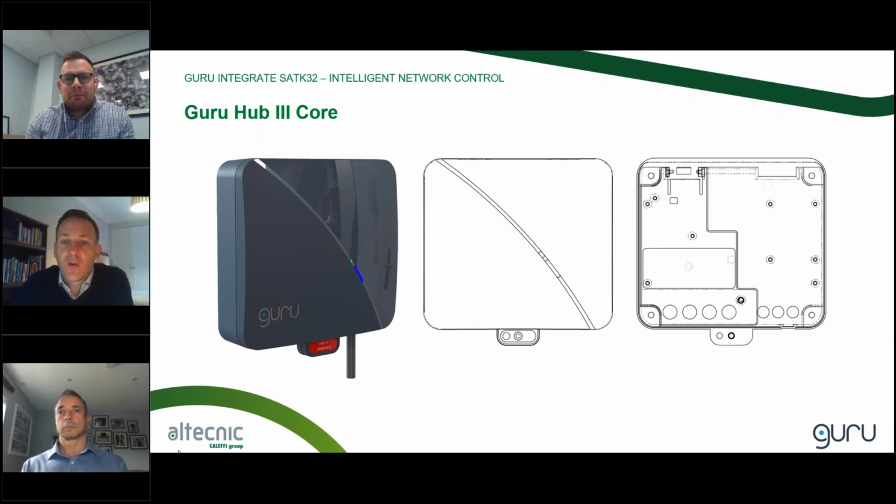It takes inputs from MBus, so heating and cooling meters or other utility meters, Modbus, and pulse inputs if we need to. We tend to counsel against using pulse meters or pulse output meters, but sometimes that's what we find when we're on site, so we need to deal with it. And it's also got relays built inside, and those relays are multi-purpose. They can be used to send an enable or disable signal to the HIU, as Neil was describing before. They can be used to actuate motorized 2-port valves that are mains powered, etc.